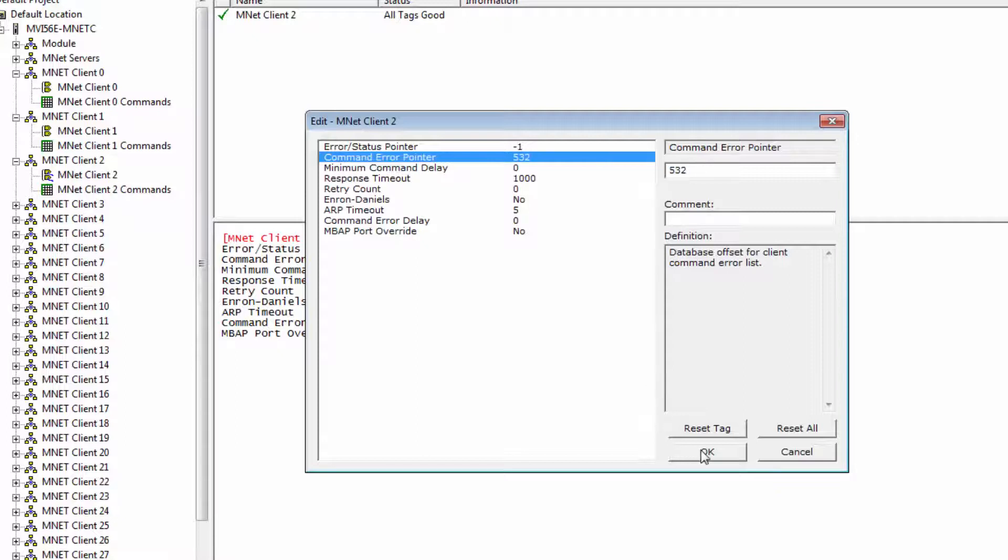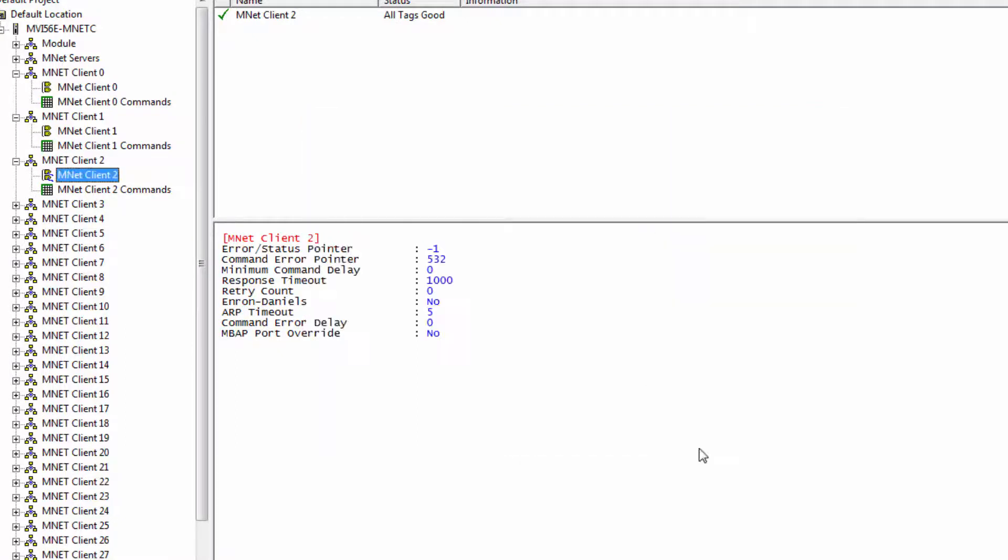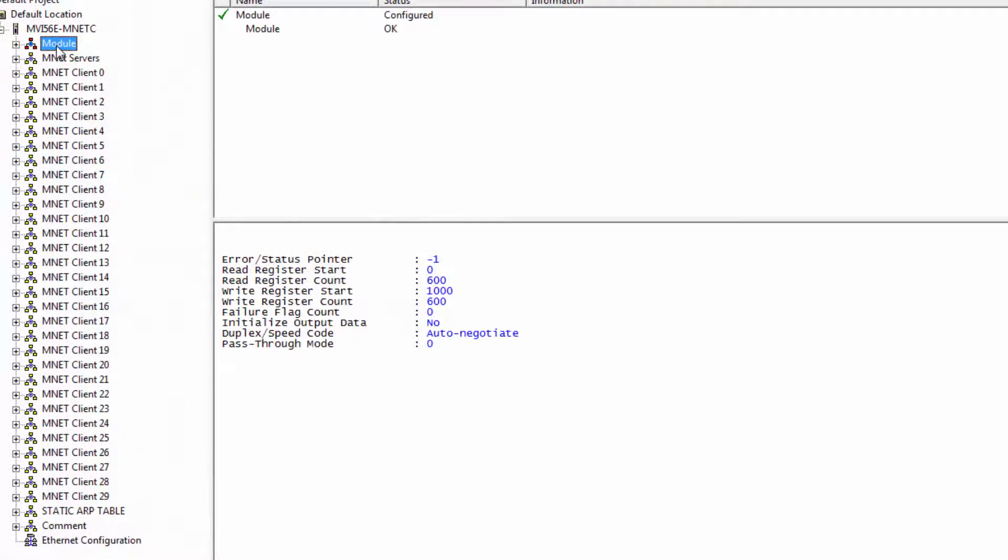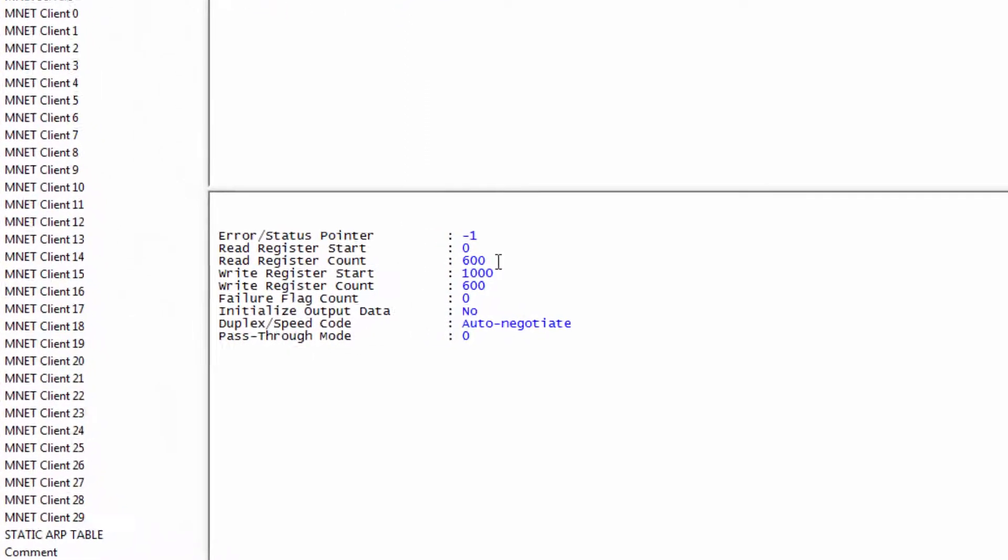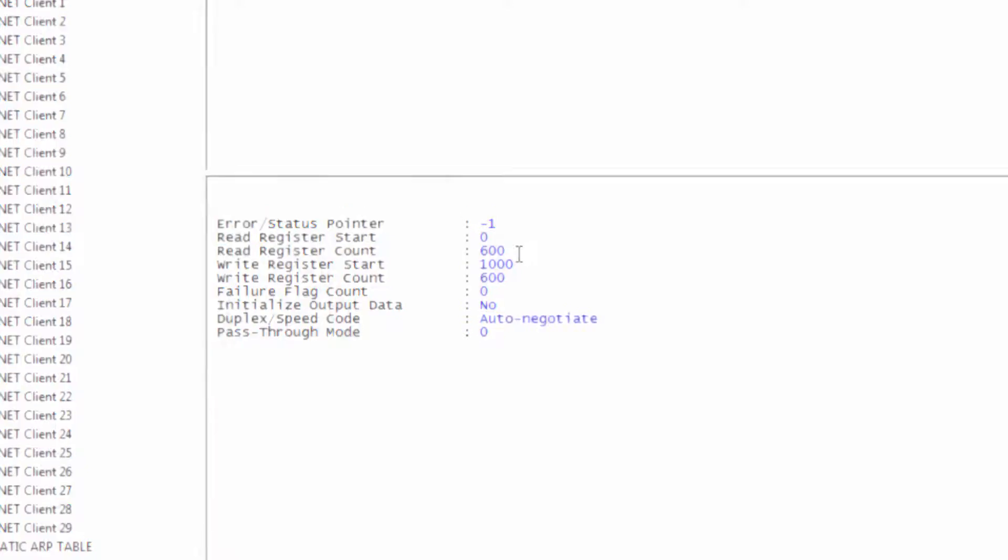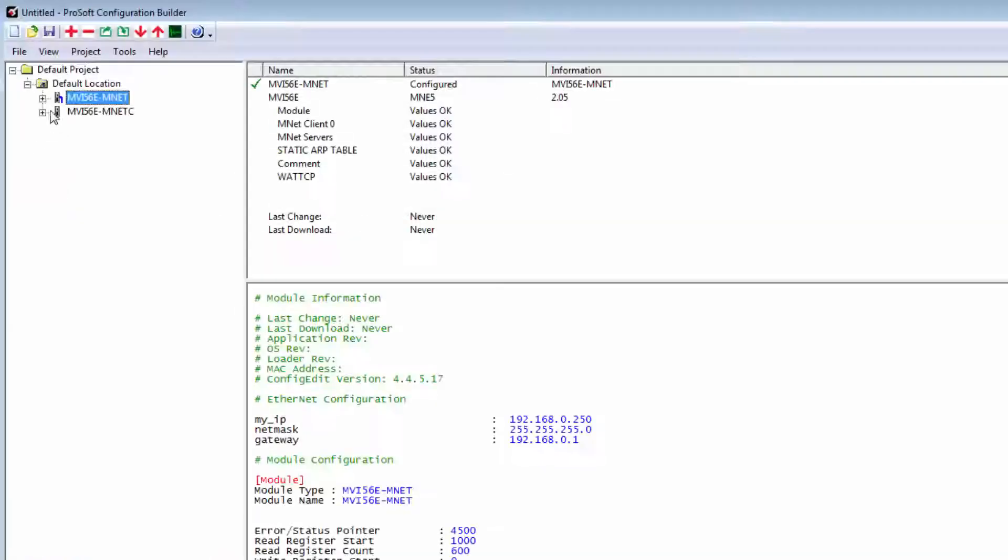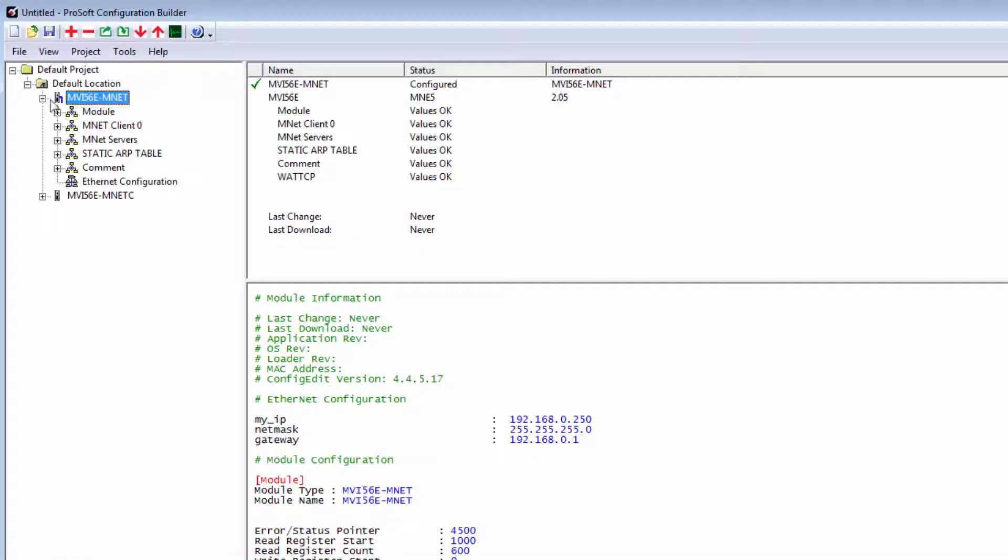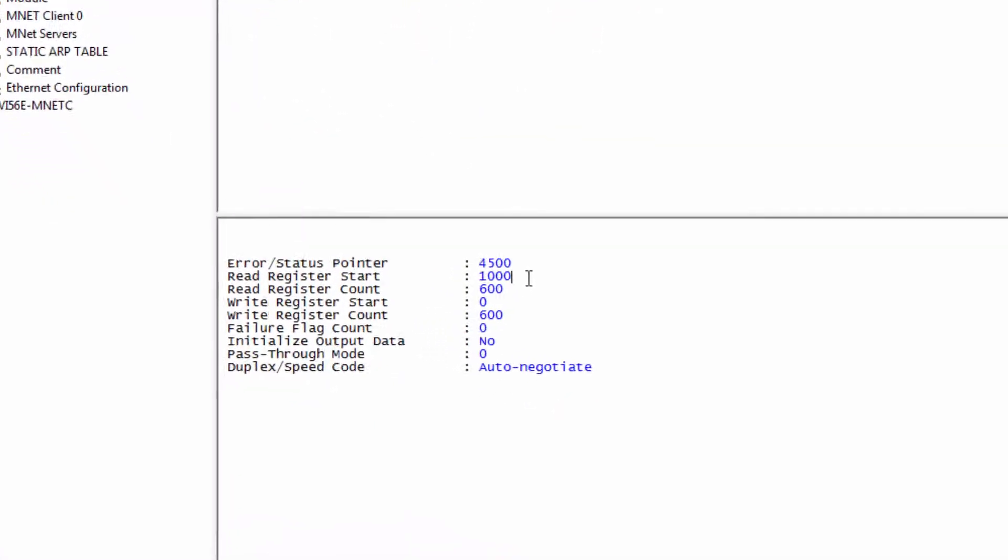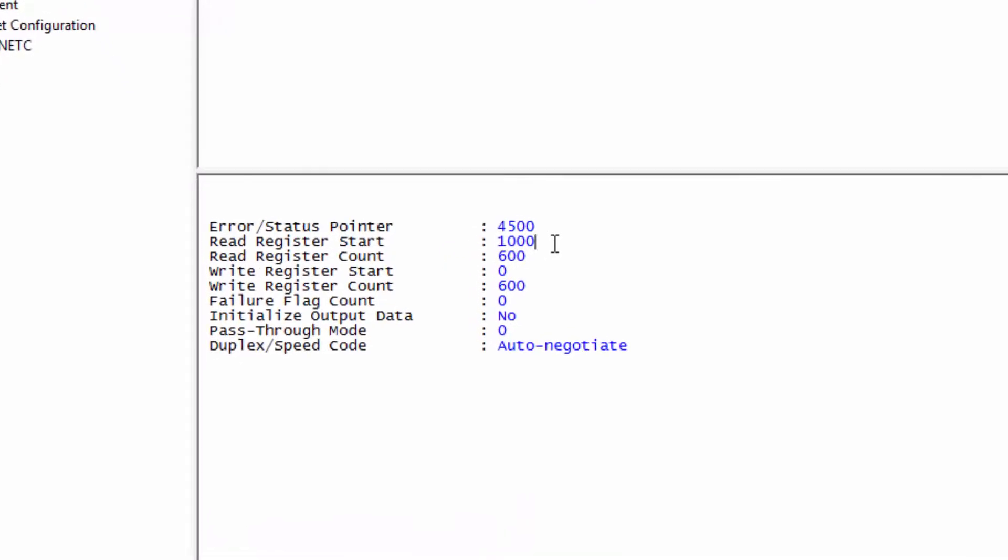Note that this default starting register for the Read Data section of the module may be different depending on what module you have. For instance, the Mnet C has the Read Data starting at address 0, 0, as we've just seen. The MVI56E Mnet, however, has its Read Start Register set to 1000 by default. So keep that in mind. So that is how you configure the Command Error Pointer with the majority of our products.